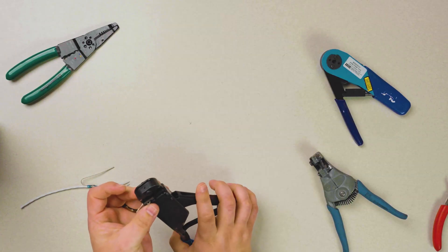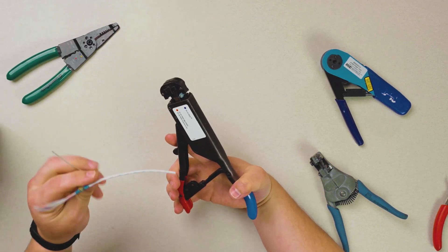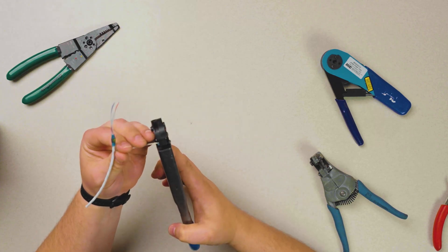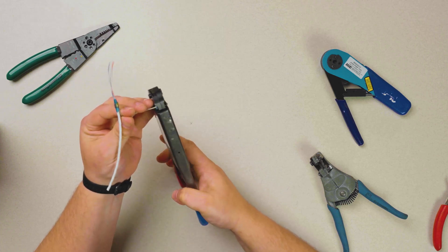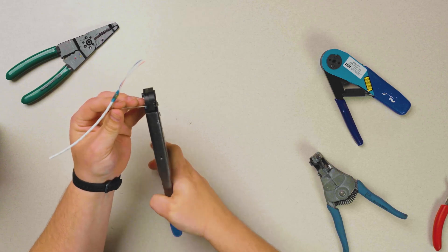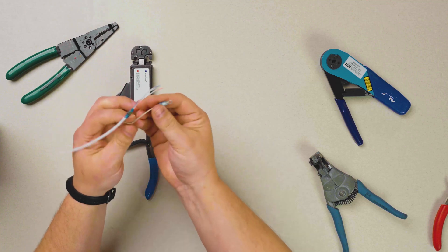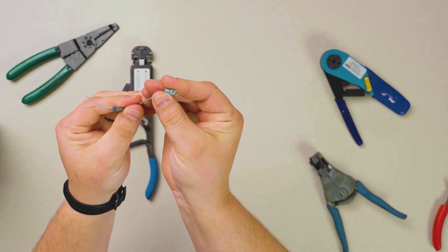When we utilize the automatic ratcheting style crimping tool for our ring terminals, again we establish that the shielding is all the way penetrated through. Position it correctly. And we can see we have maximum engagement and there's very little, if any, deformation.